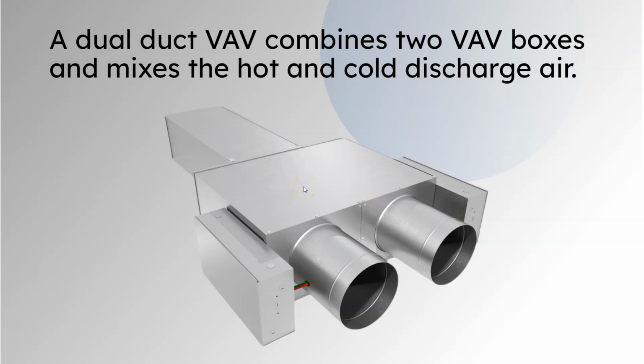This is a dual duct box. All a dual duct box is, basically, is two VAVs put together. These sides go to the air handler. Typically, there'd be cold air on this side and warm air on this side, and they mix together here depending on how much you open each damper, and then this blows out to the space. This is seen in a lot of older buildings and hospitals in general that just run boilers all year round. It's kind of an inefficient system just because you do have to run a boiler all year round to get the hot air coming through this side and have the chillers running all year round to have the cold air coming through this side.